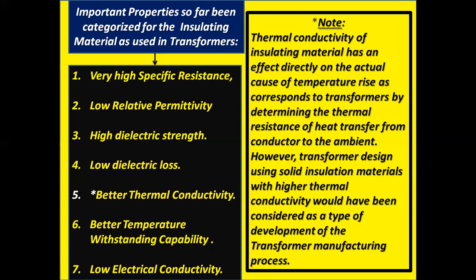Thermal conductivity of insulating material has an effect directly on the actual cause of temperature rise as corresponds to transformers by determining the thermal resistance of heat transfer from conductor to the ambient. However, transformer design using solid insulation materials with higher thermal conductivity would have been considered as a type of development of the transformer manufacturing process.